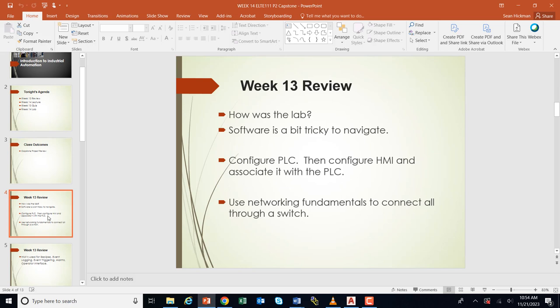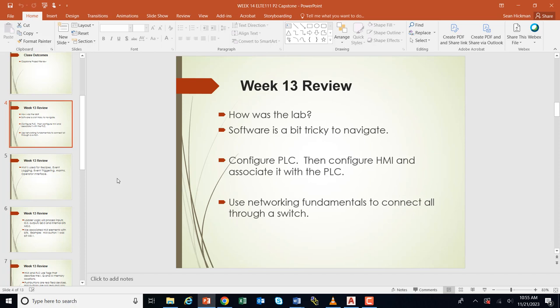Let's go back to week 13, which was the HMI. The HMI was paired with the PLC. The software is a new type of software, so getting through it in the browser, pulling out your screens, doing your tags, everything takes a while. But everybody seemed to get through and make it work pretty well. Remember, you have to configure a PLC first, then configure the HMI, then associate the two together. When you go to network, you see a green line between the PLC and the HMI, meaning the ladder logic of the PLC can talk to the HMI. We used basic networking fundamentals to connect everything through a switch so everything was talking.